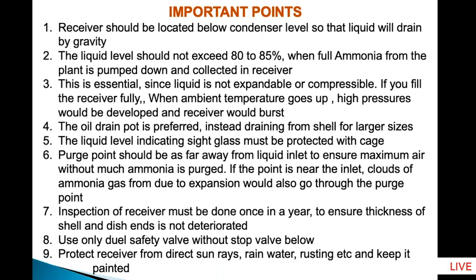The next important point, as I mentioned: the receiver should be located well below the condenser level so that liquid will fall to the receiver by gravity. This is important because the condenser pressure and receiver pressure are the same. Do not keep the receiver next to your condenser. I have to mention my personal experience. In a lot of ammonia plants, especially with evaporative condensers, people tend to keep it next to the condenser, and then your liquid will not get drained into the receiver. It will accumulate in the condenser. It will affect the condenser performance.